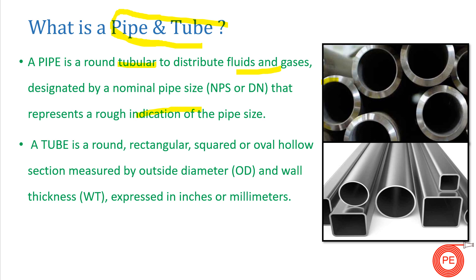Pipes are designated by either nominal pipe size or DN. This nominal pipe size and DN are a rough indication of pipe size. For example, if we need a DN 200 pipe, it doesn't mean the pipe size is exactly 200 mm. For a DN 200 pipe, the outside diameter is about 219.1 mm, and the inside diameter will vary with the change in schedule number.